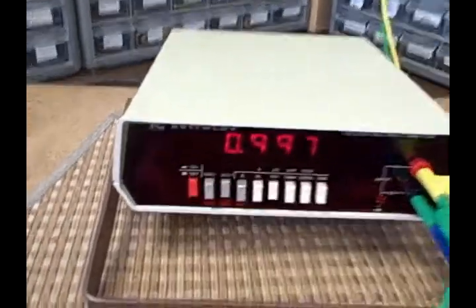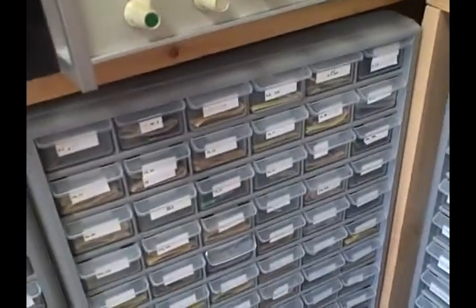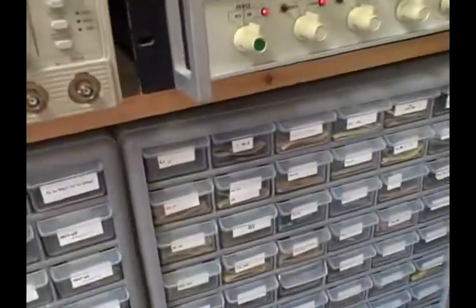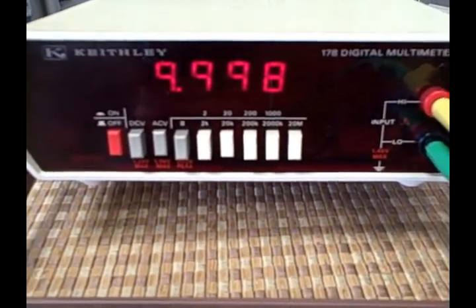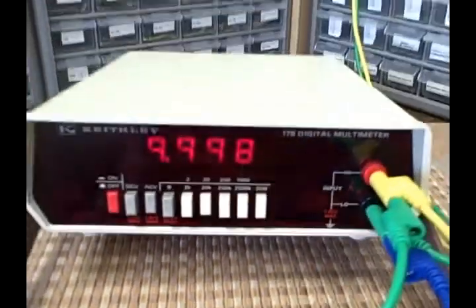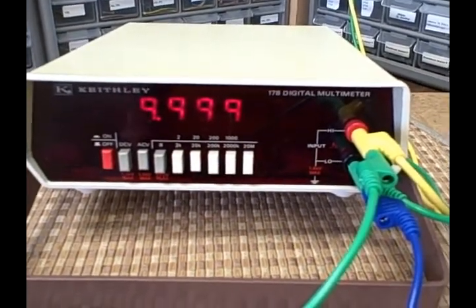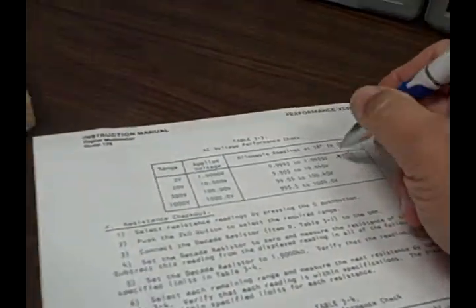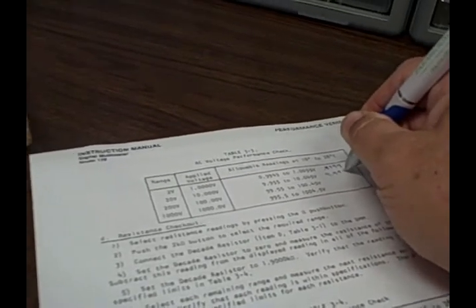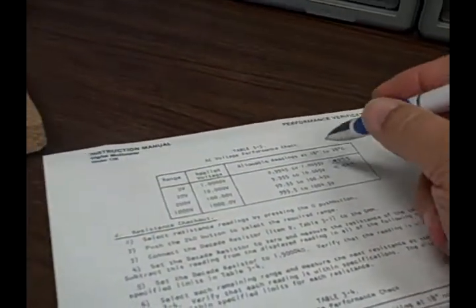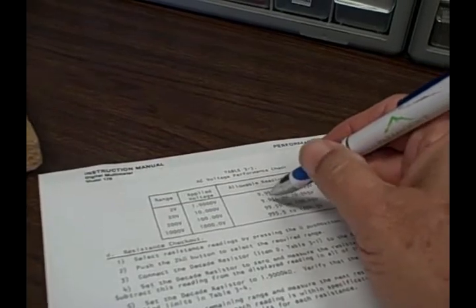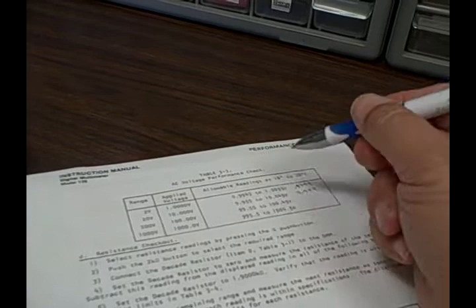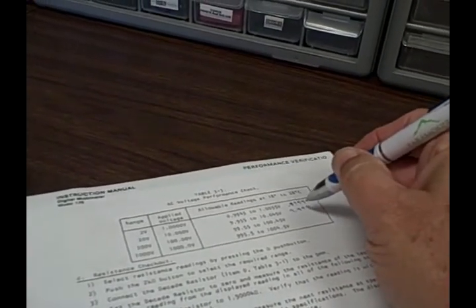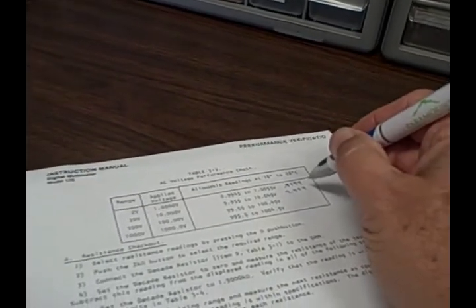Okay. And I want to up the voltage here to 10 volts. Okay, we have 10 volts, 10.000. We're getting 9.999. Yeah, sometimes a flashing 8, but .999, and that would put us in the middle again. We would be good if we read 9.955 to 10.045 volts, and we are reading 9.999, a millivolt off of perfect 10 volts. So again, perfect on both ranges. Let's go to the 200 volt range.